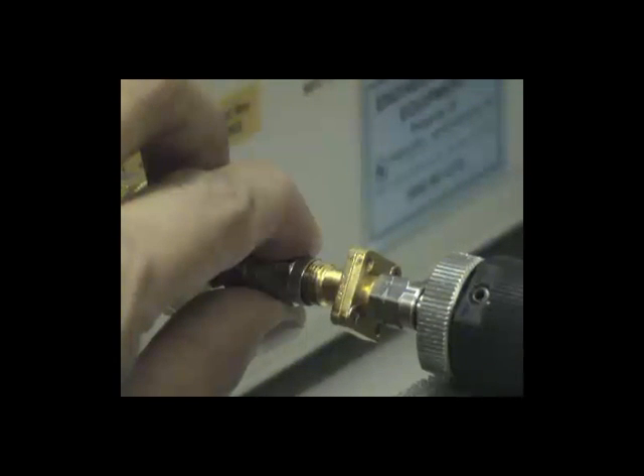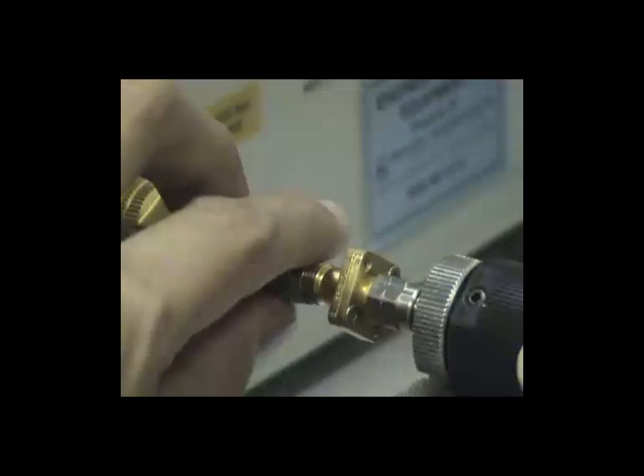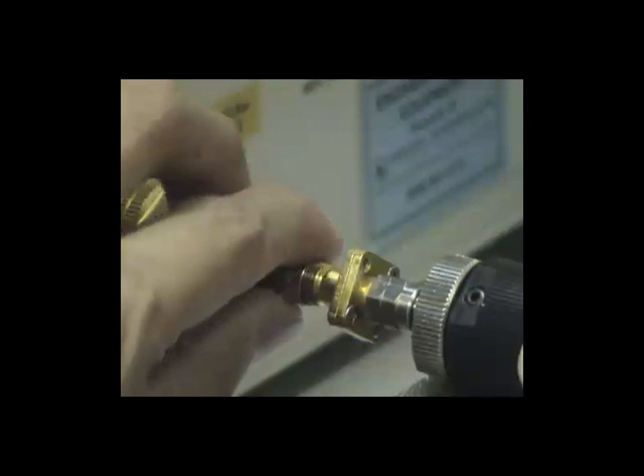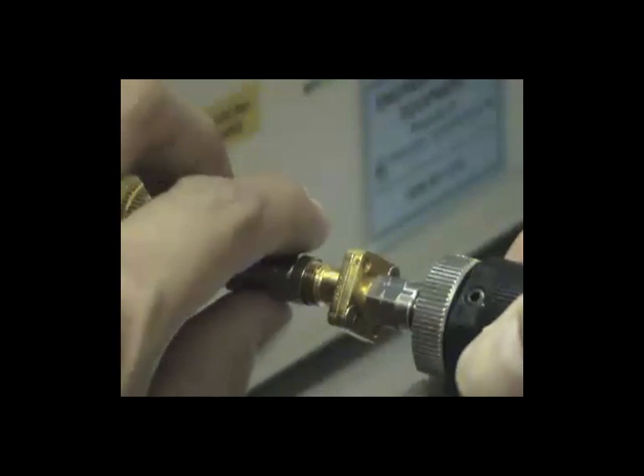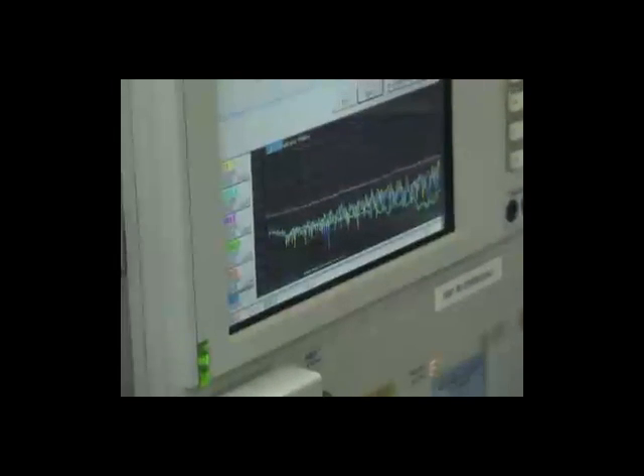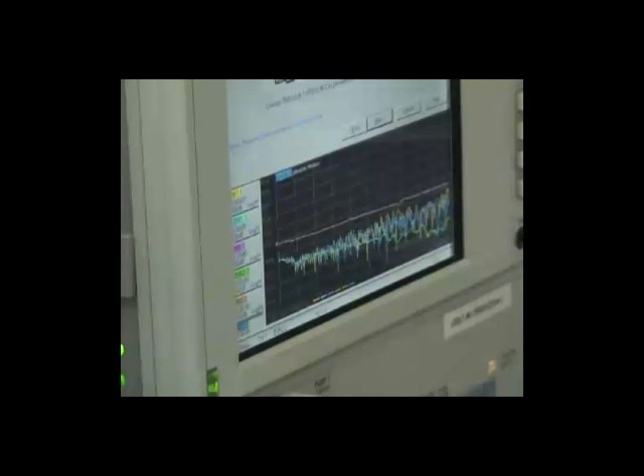I slowly slide this on and try to look for the familiar trace when you do the connection. If you see something going up or if you see a spike or a dip, then it means that something is not aligned right. Familiarize with the standard trace that way you know what you're looking for and you can stop if something is not right and back out. It generally takes time to do a TRL, so take the time to perform the calibration.